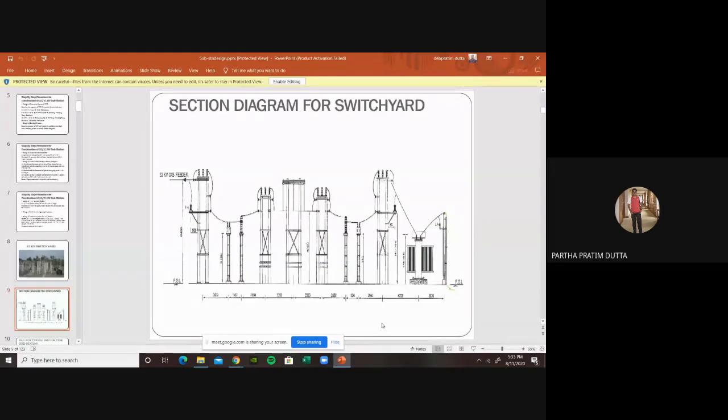That is the standard protection system or standard switchgear layout design for any 33 by 11 kV substation. Again, I am showing you that 33 kV feeder, LA, main isolator with earth switch. Obviously every isolator has got an earth switch with it. Then CT, then VCB, then again isolator, then VCB, then isolator, and then transformer.